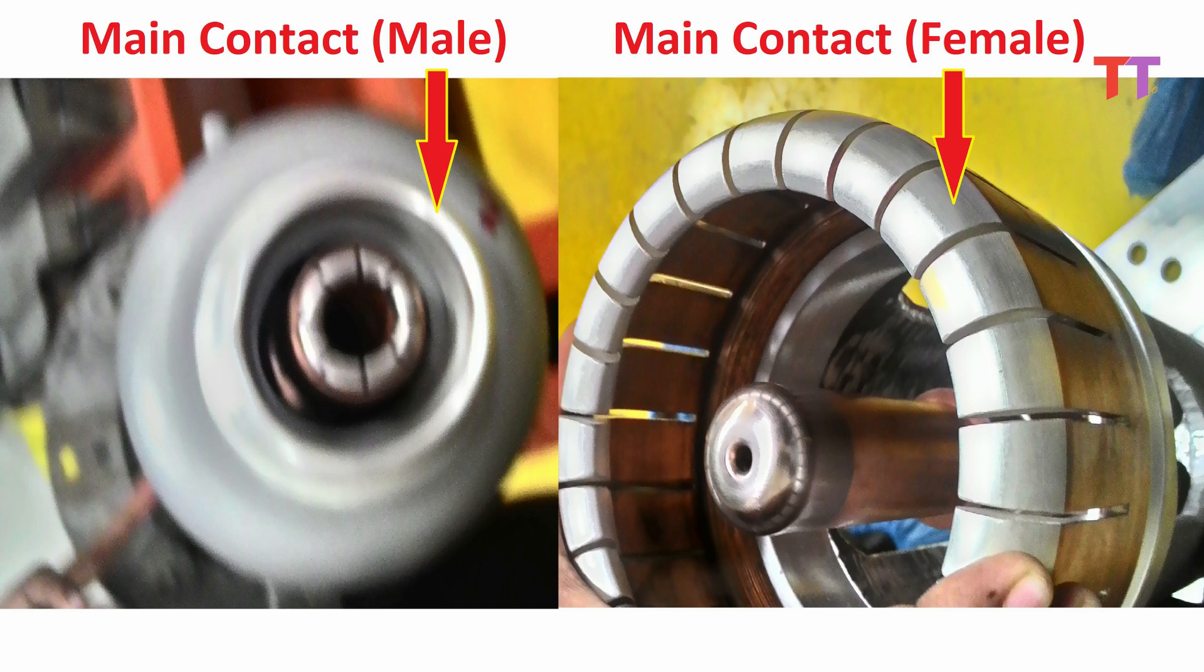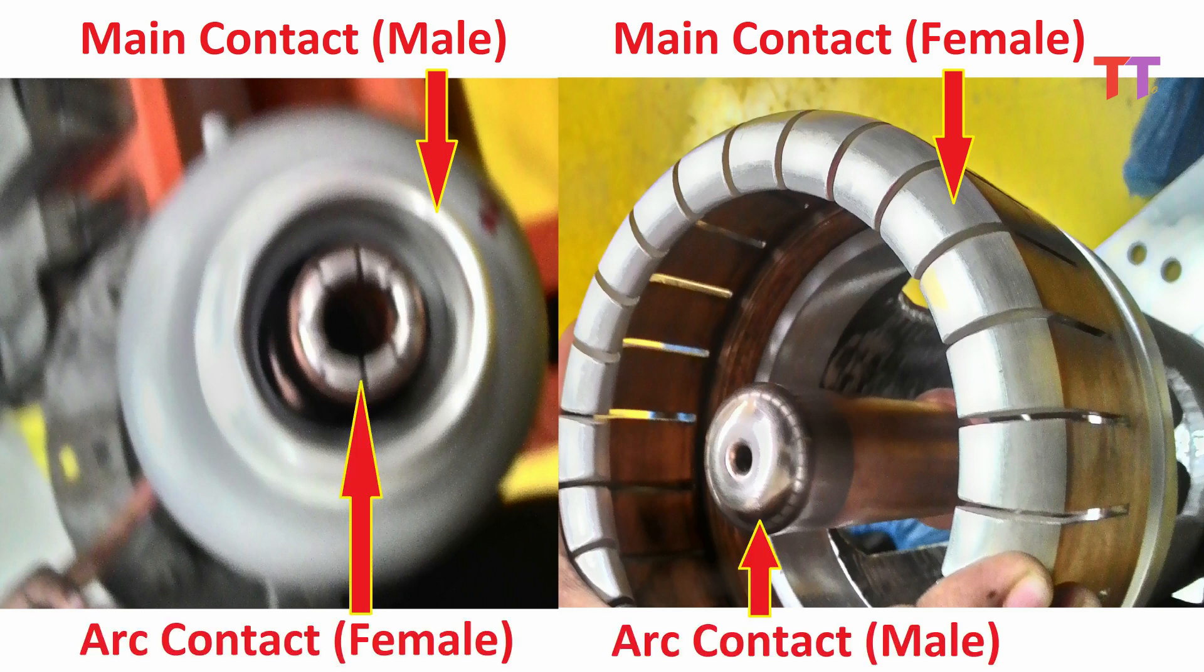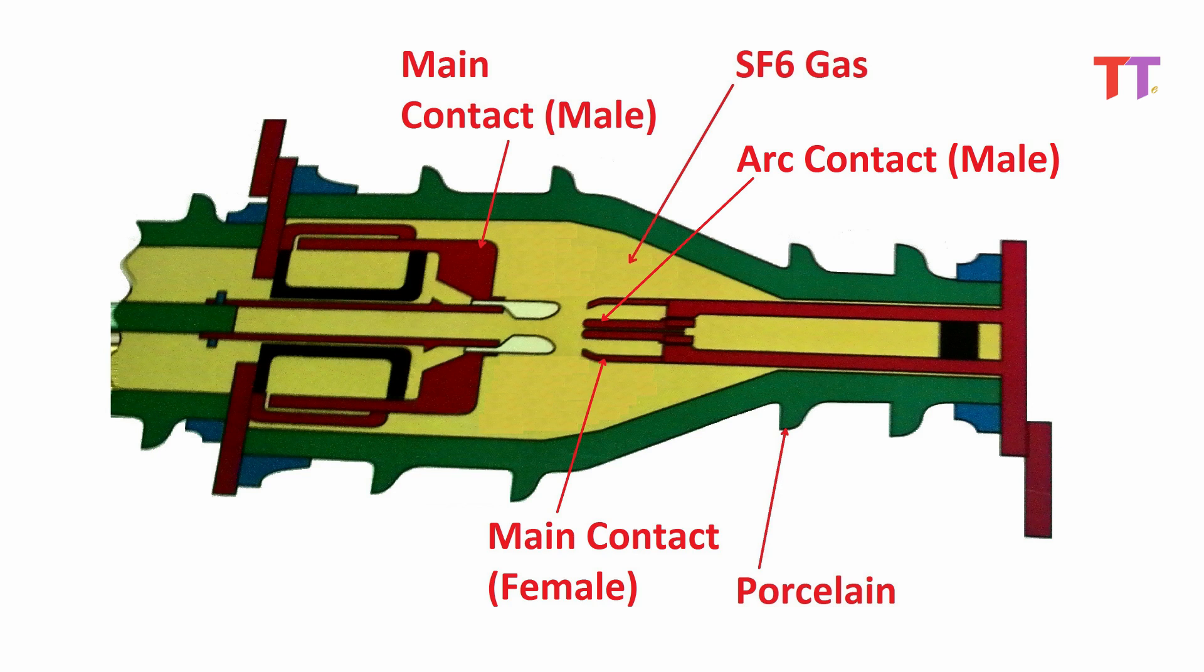This is how these two contacts look like. If we look closely we can see there are two more contacts relatively smaller. These contacts are called as arc contacts. This one is male arc contact which is fixed and this other one is female arc contact which is moving.